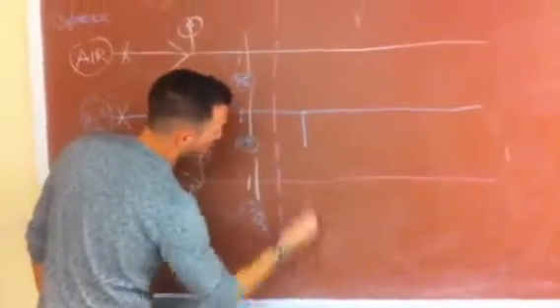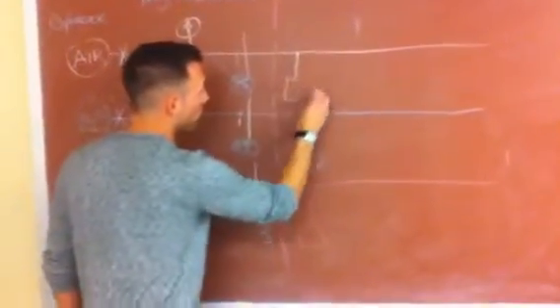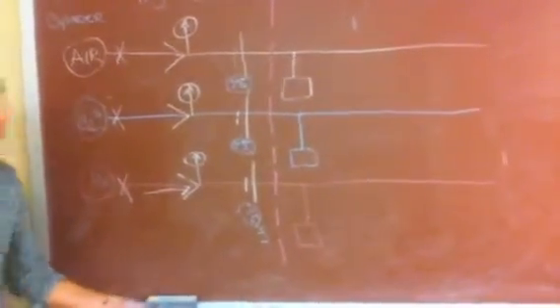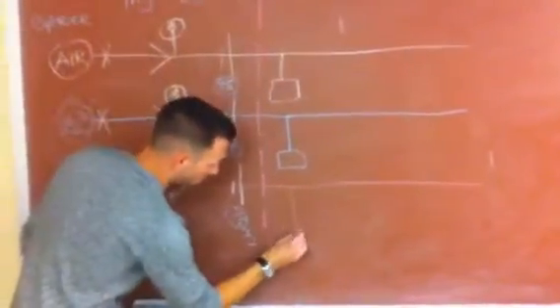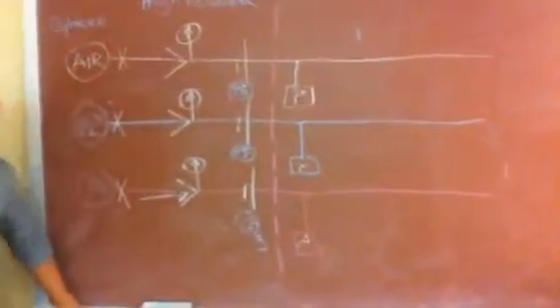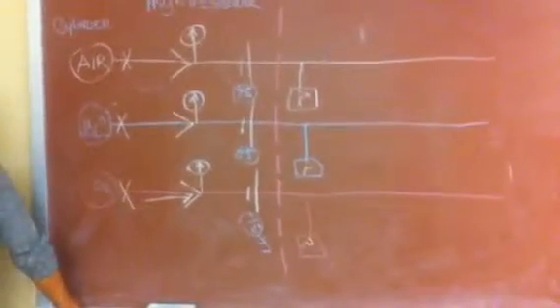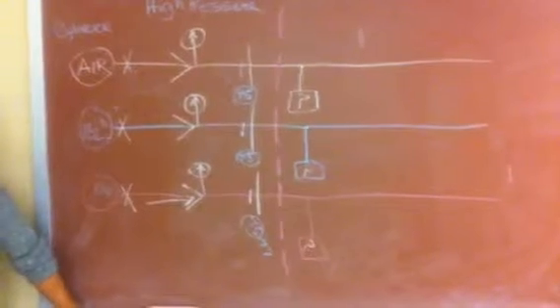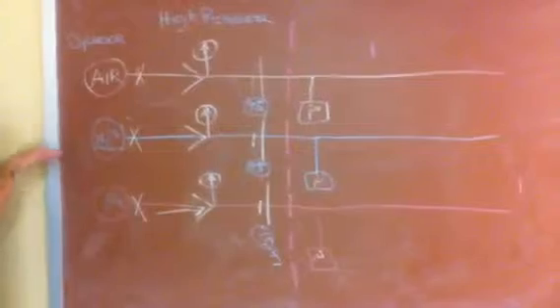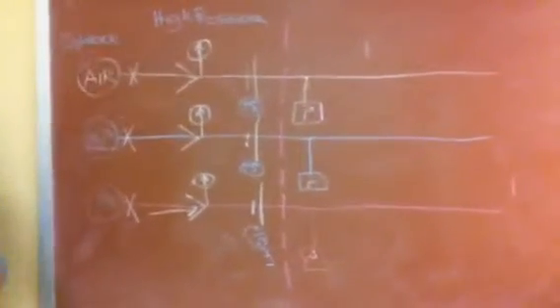say this is the pipeline. Okay? This is coming directly from outside, through the wall, right into the back of your machine, hooked into the hose. Okay? So this is coming from your central... What is it called when it's outside? Central oxygen tank. And it's coming through hoses, through pipes, through a whole system, going right into the OR wall. And you plug a hose into the OR wall, it's a certain color, and it fits. And then you have your pipeline pressure.